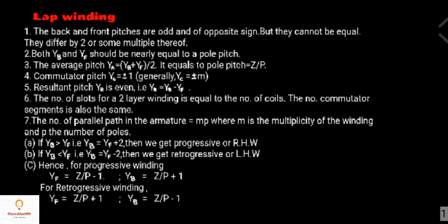If back pitch is greater than front pitch — that is, back pitch equals front pitch plus 2 — then we get progressive winding, or right-handed winding. For progressive winding, front pitch equals pole pitch minus 1 and back pitch equals pole pitch plus 1. For retrogressive winding, front pitch equals pole pitch plus 1 and back pitch equals pole pitch minus 1.